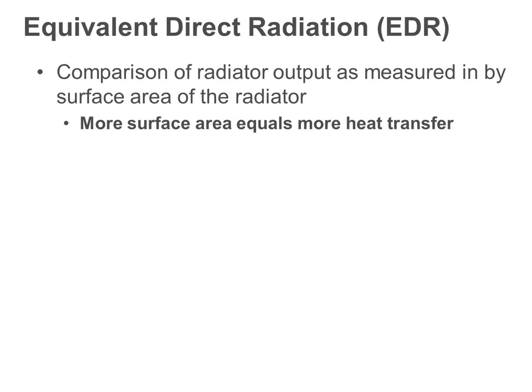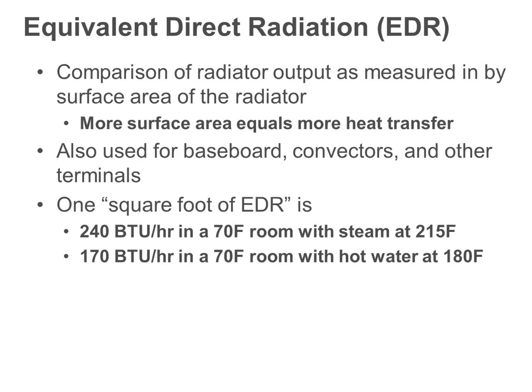That's why, if you think about it, a radiant floor system is one of the best heating systems because of the amount of surface area we have. You do a large manufacturing firm or whatever, 100,000 square feet, you've got a 100,000 square foot radiator you're walking around on, it's going to keep you warm. You put a bunch of little terminal units on the wall, they're going to have different areas, different amounts of heat output, but now you're doing convective, maybe you have fans on it, you have different things going on. But basically, you're trying to find a number, okay?